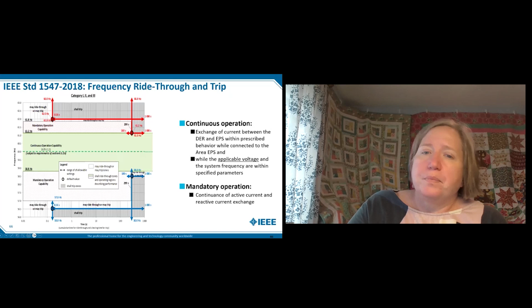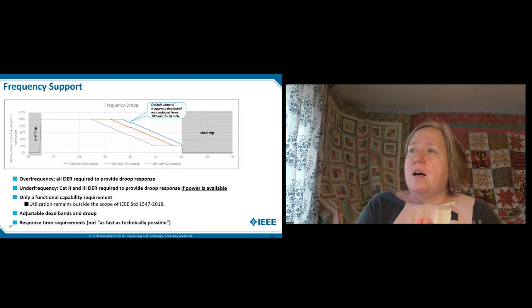So, frequency support. All DER is required to provide droop response for overfrequency. Cat 2 and Cat 3 DER have to provide droop response for underfrequency if power is available. There's only a functional capability requirement. Once more, using this is up to the area EPS operator. It has adjustable deadbands and droops, and there are response time requirements. So this can be fairly slow to operate because it is droop.